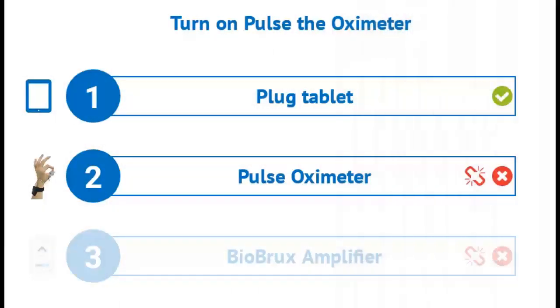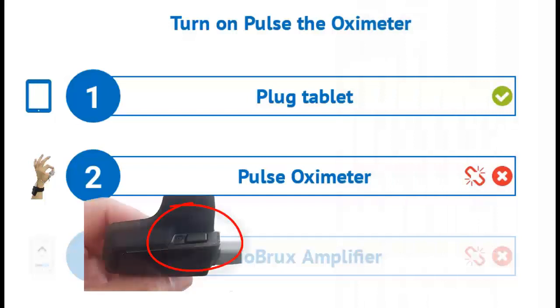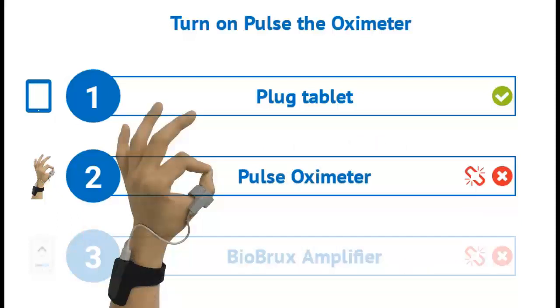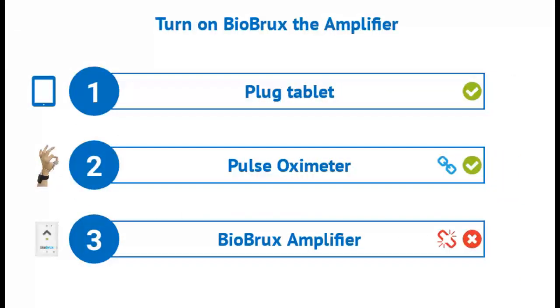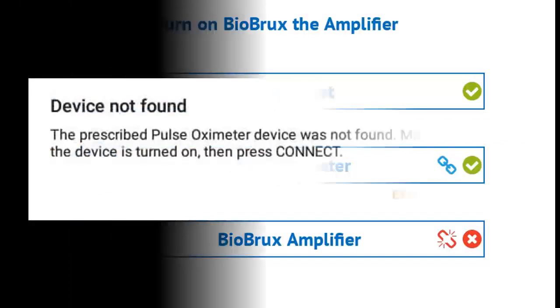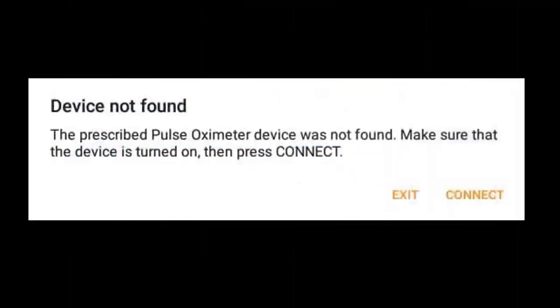Now that the tablet is plugged in, you will be prompted to turn on the pulse oximeter. Place the thumb sensor on your non-dominant hand, then wrap the oximeter around your wrist and secure using the buttons. When you turn on the wrist oximeter, press the button on the side of the oximeter as shown until you see a red light on the thumb sensor. If the green check mark does not appear, you will see a prompt to reconnect after you confirm the oximeter is turned on and you see a red light is on the thumb sensor.